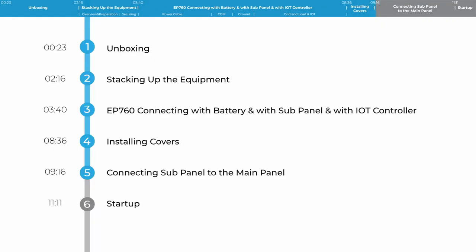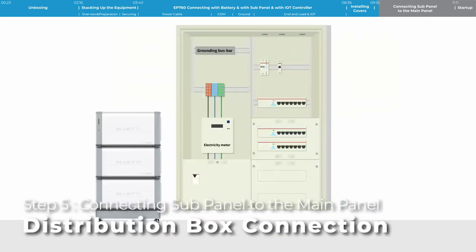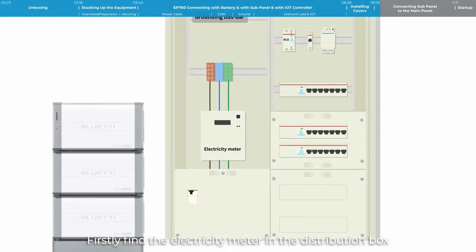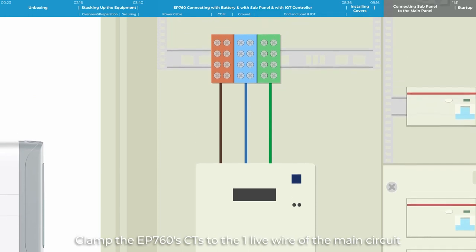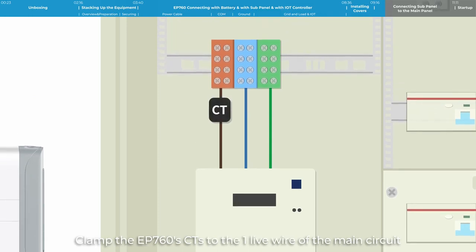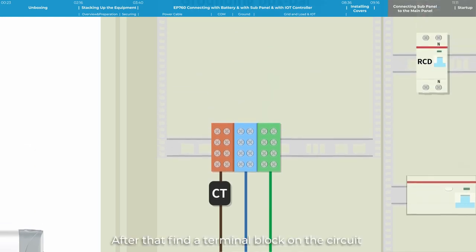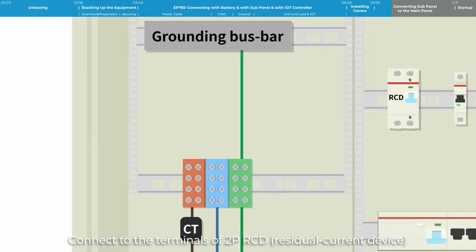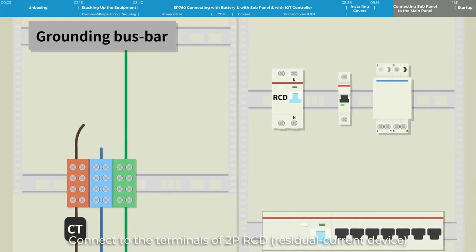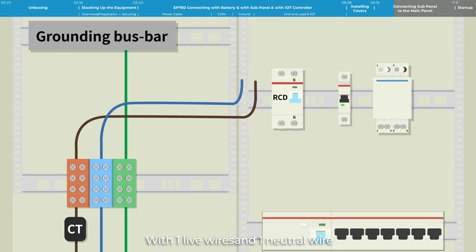Step 5: Connect with subpanel into the main panel. Firstly, find the electricity meter in the distribution box. Clamp the EP760's CT to one live wire of the main circuit. The arrow points to the grid. After that, find a terminal block on the circuit or somewhere around the bus bar. Connect to the terminals of 2P RCD, residual current device, with one live wire and one neutral wire. The sequence from left to right is L N.